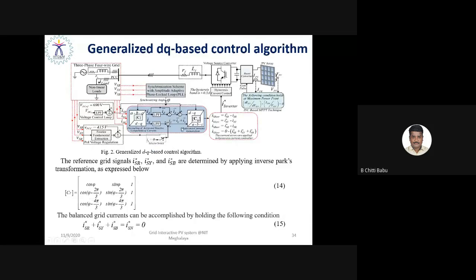That is what. And moreover, as you are transforming DQ to ABC, this transformation is called the Park transformation. You can use that. For such a transformation, you always need to estimate or extract the phase component, called the synchronizing angle, phi. So the extraction of phi is very important. That is possible with the help of synchronization, the adaptive phase locked loop. Whenever a three-phase non-linear load is connected, obviously your three-phase grid current is distorted. So extracting the fundamental component when the grid is under abnormal or distorted condition is very difficult. That is why we propose an adaptive phase locked loop, so that you are able to precisely extract the value of the phase angle phi relevant to the fundamental 50 Hz component, so that you are able to implement your desired control algorithm.